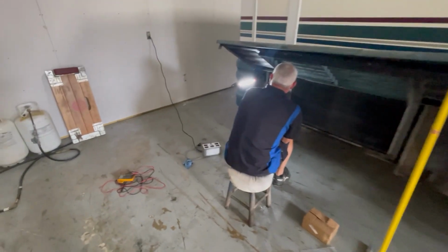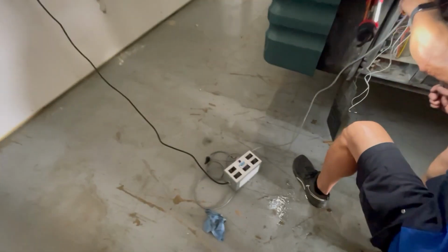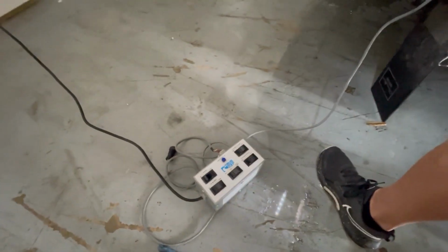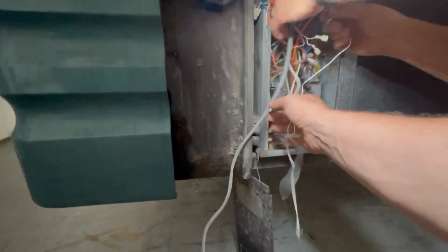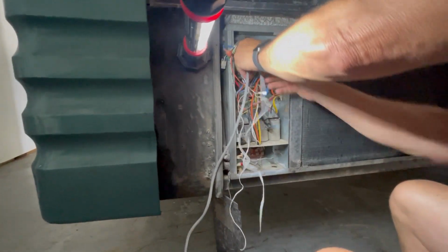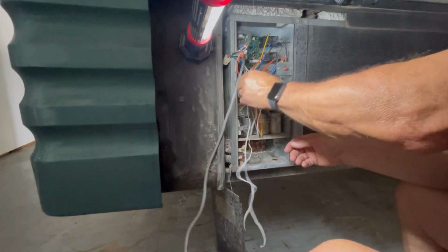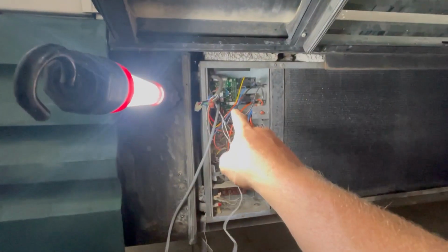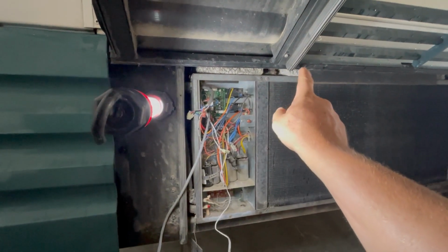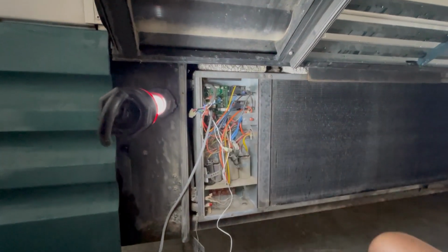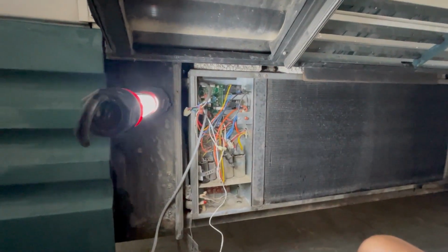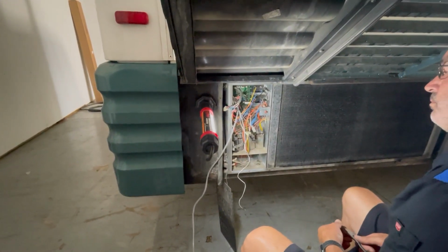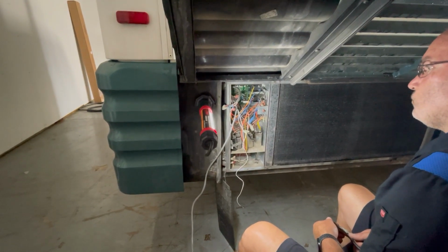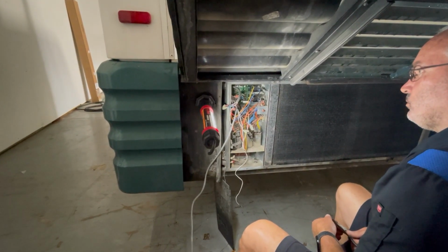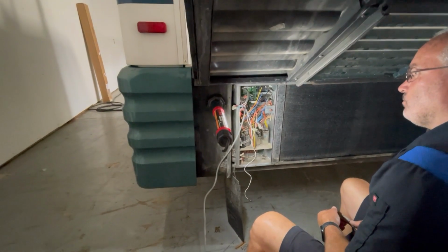Okay, so we did run this basement air on our test box. The one thing we noticed was that we did not have our freeze circuit. Lewis has gone in here and put two separate freeze sensor wires on here to test this, and nothing has changed, so we do have a bad freeze circuit. We checked the wiring up at the thermostat, and we do have power on one of the grays, but we don't have power on the other gray, which tells us there's a problem with the freeze circuit in that control board. This is the original control board, so we're going to change that and update it to the new one. They also had the original thermostat from 2000, and we're going to update that too, because typically there's some problems we see with the circuitry in that board. So we're going to change all that out now.